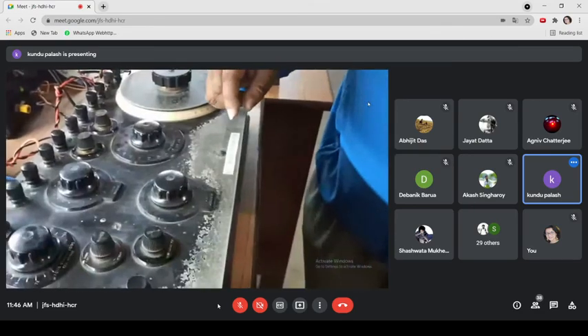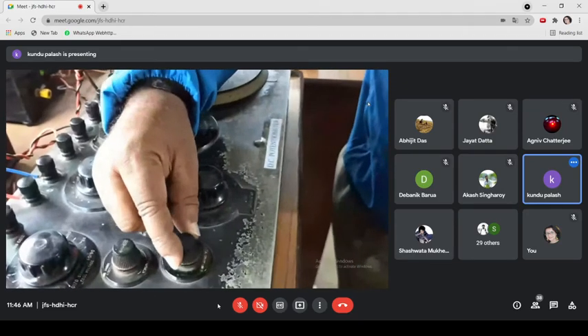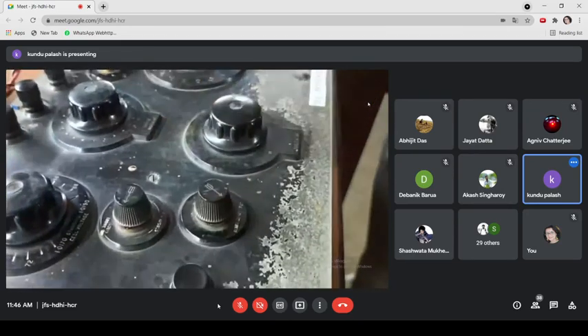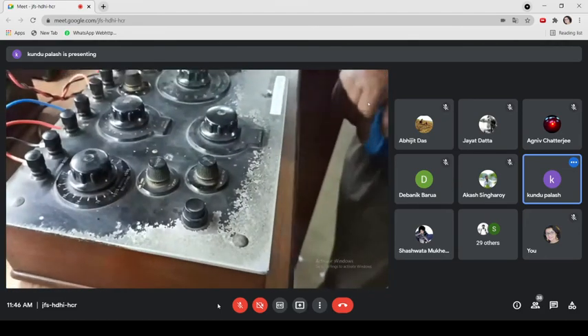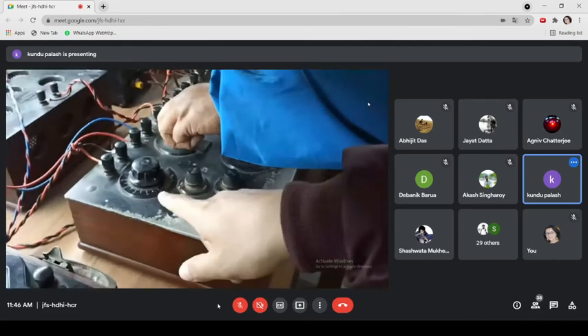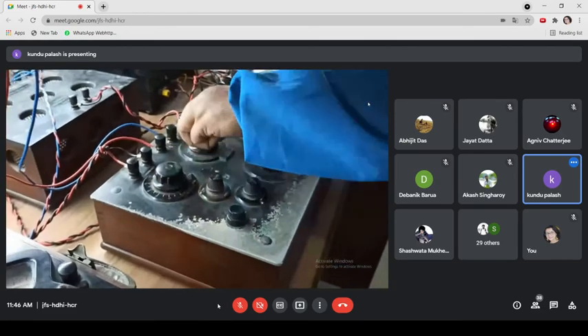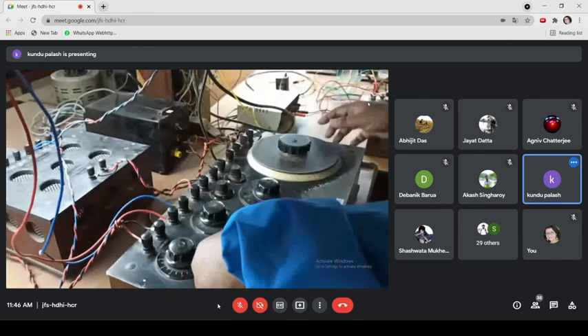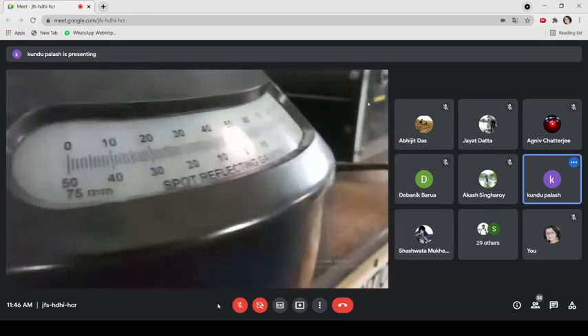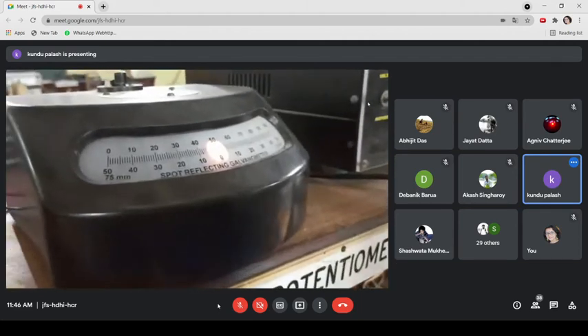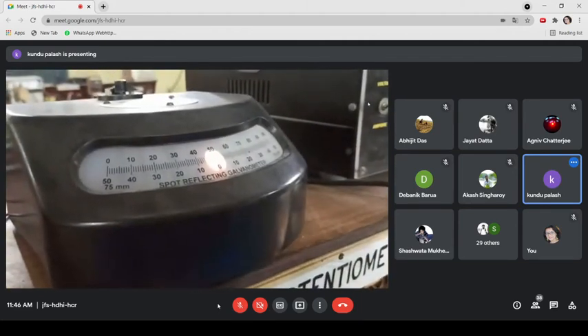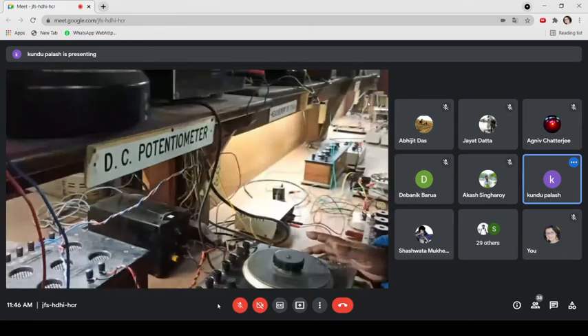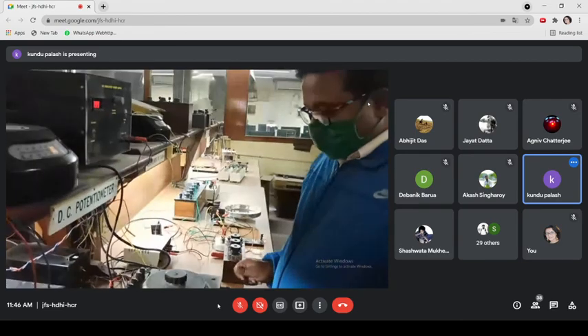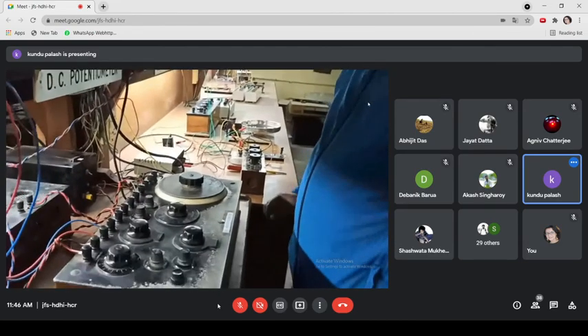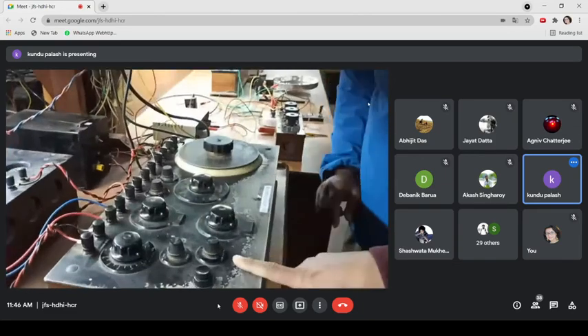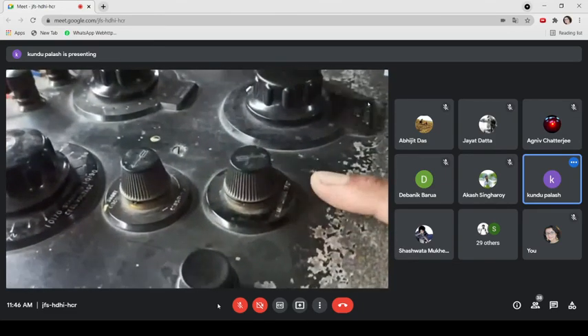So before doing the test, we need to standardize this potentiometer. So we are putting it in standardized mode, and by tuning this standard cell voltage and the rheostat, we will standardize this potentiometer. As you can see, there is no deflection in the galvanometer. So we can say that the DC potentiometer is standardized, and you can start the test. So we are switching this to the test mode.